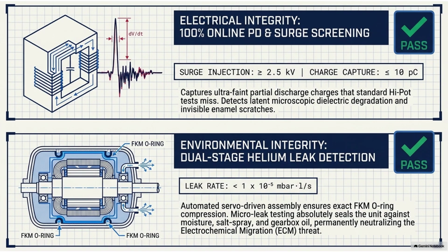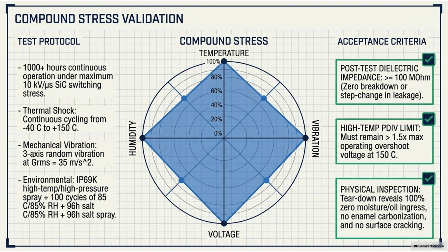Okay, so the coils are wound flawlessly, and now they have to be locked into place and insulated further using vacuum pressure impregnation, or VPI. So what does this all mean for the resin? It sounds like they are basically forcing honey into a sponge, right? That's a good visual, yeah. Exactly. You aren't just dipping the motor in a vat of epoxy. Air is the enemy here. Any microscopic void left between the wires will eventually ionize and cause partial discharge. So the VPI process manipulates atmospheric pressure to eradicate the air entirely.